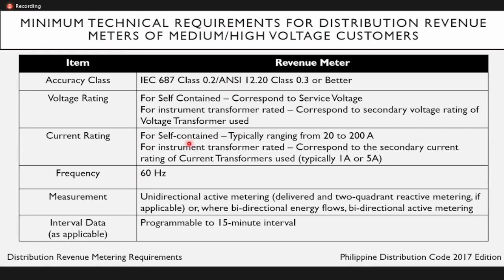For the current rating, the revenue meter for self-contained typically ranges from 20 to 200 amps. For instrument transformer rated, it corresponds to the secondary current rating of the current transformers used, typically 1 or 5 amps. The frequency of the revenue meter should be 60 Hertz. Measurement could be unidirectional active metering or bidirectional active metering for bidirectional energy flows. The interval data, as applicable, should be programmable at 15 minutes interval.